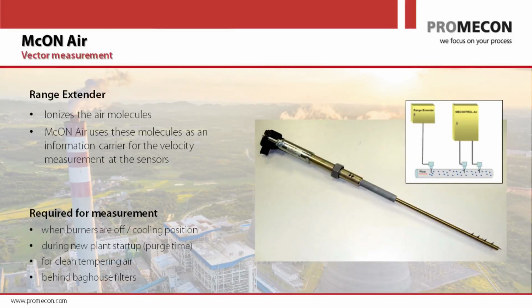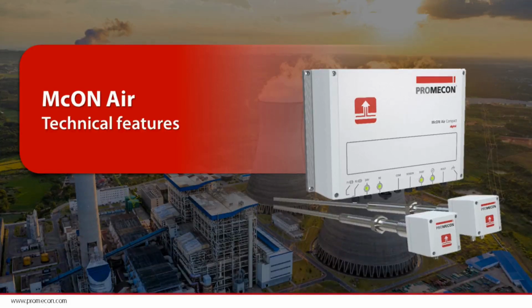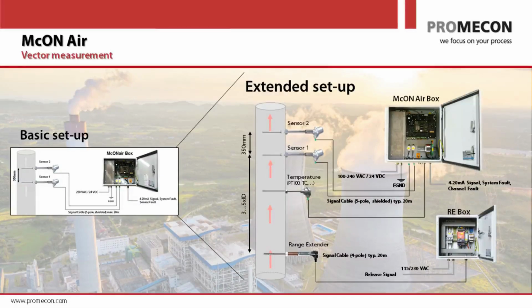Here you can see such an example of a range extender as it is installed in a duct. Now, just a few things. How does this thing look when it's installed? What you can see here is basically the setup that is usually used in a power station. You have two sensors that go to the air box. The sensors carry the raw signal to the box, and the range extender is installed upstream, so you can measure the flow with an ionized gas if there's no dust.